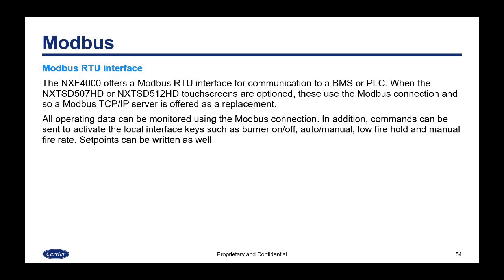The NXF4000 offers a Modbus RTU interface as standard for communication to a BMS or PLC. When the NXTSD507 HD or 512 HD, the 7 and 12 inch touchscreens, are optioned, these use that Modbus connection, and so in turn a Modbus TCP/IP server is offered as a replacement out of the touchscreens. All operating data can be monitored using the Modbus connection. In addition, commands can be sent to activate the local interface keys such as burner on-off, auto manual, low fire hold, and manual firing rate. Set points can also be written over the Modbus interface.